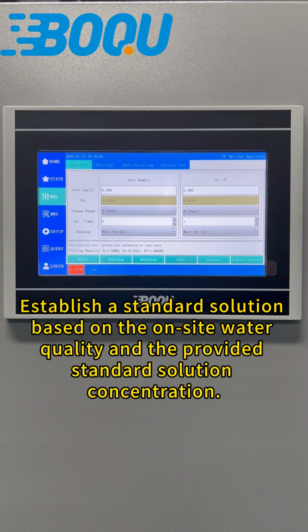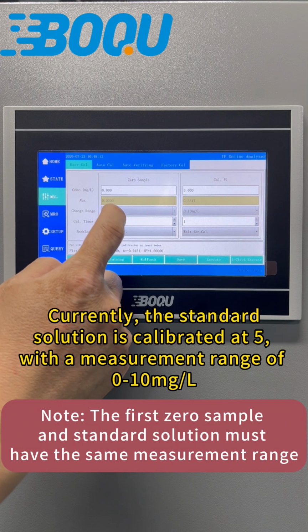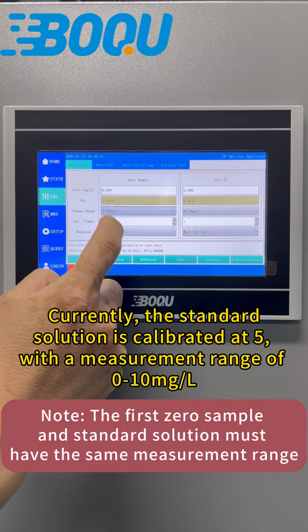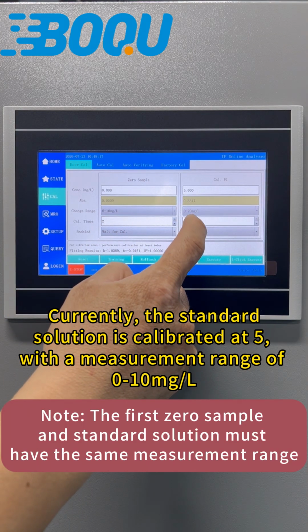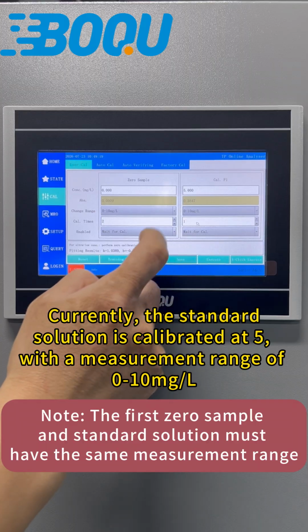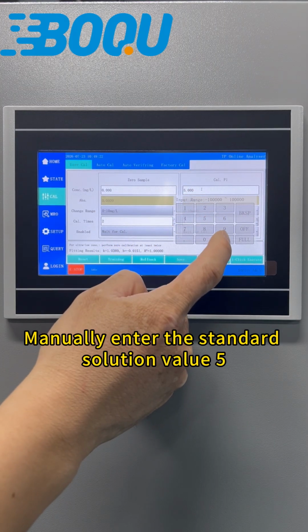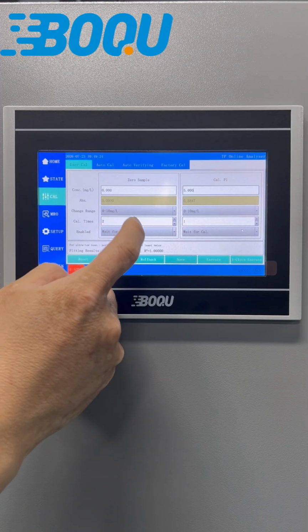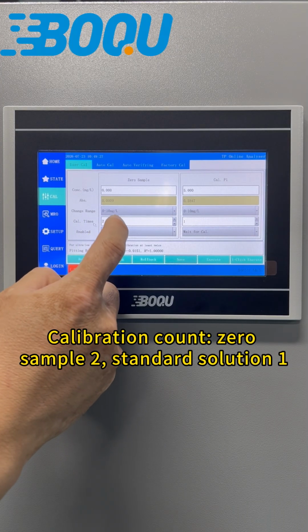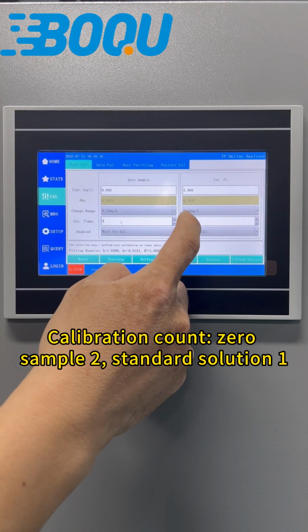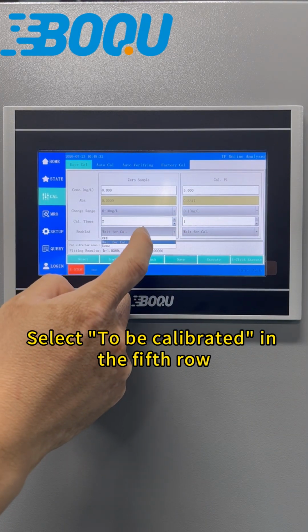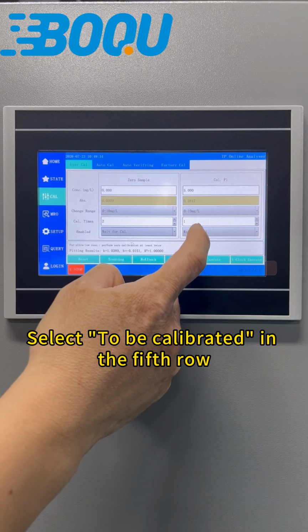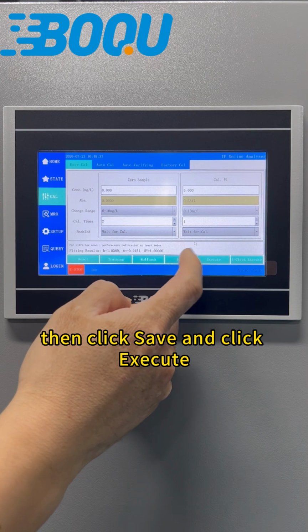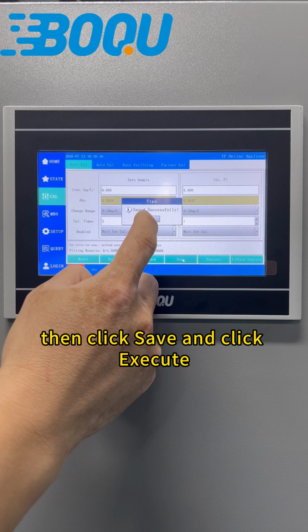Establish a standard solution based on the on-site water quality and provide the standard solution concentration. Currently, the standard solution is calibrated at 5 with a measurement range of 0 to 10 milligrams per liter. Manually enter the standard solution value 5. Calibration count zero sample 2, standard solution 1. Select to be calibrated in the 5th row. Then click Save and click Execute.